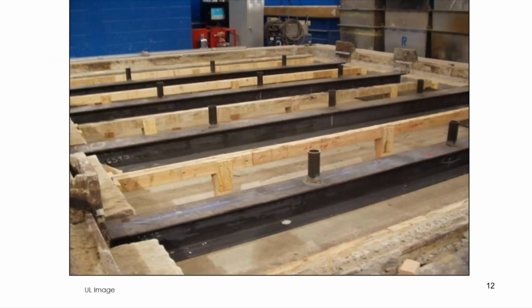So let's look at the construction and testing of a typical beam assembly. This next series of photos represents beams which are used to support a steel deck concrete floor assembly. We're looking at some photos taken at UL's Northbrook, Illinois testing facility. UL uses concrete and masonry test frames for the construction and testing of their assemblies. In this case, we've got this concrete masonry test frame around the perimeter of the assembly. We've got 4 beams spanning the short dimension of the furnace.